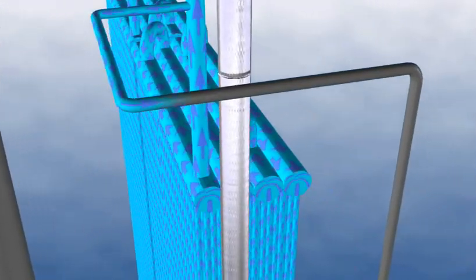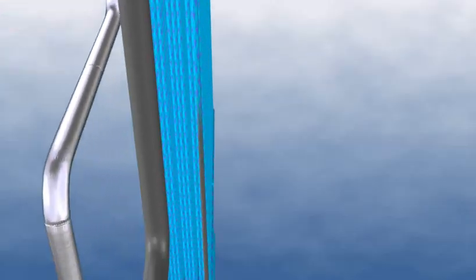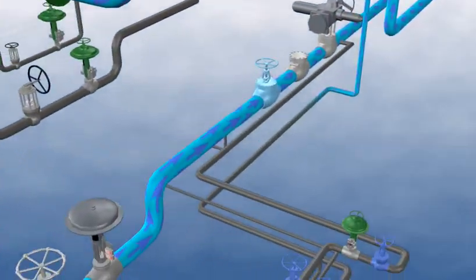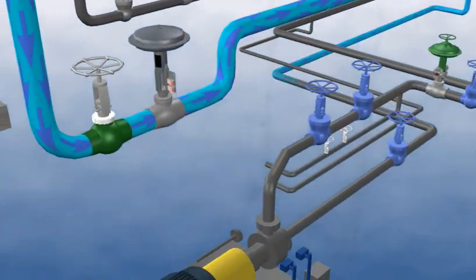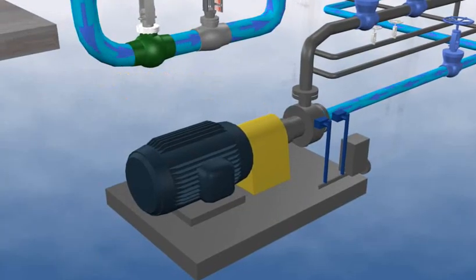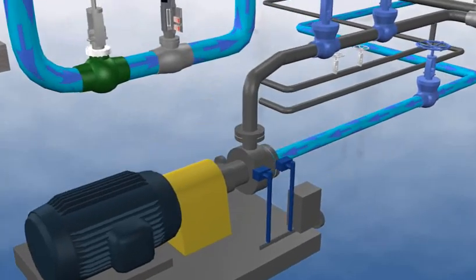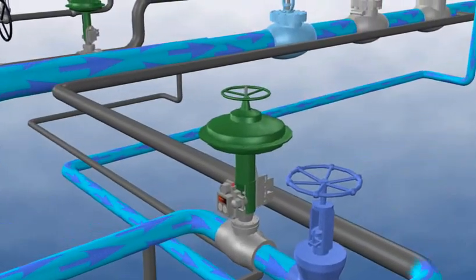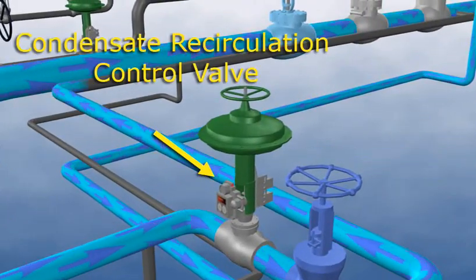A system has been provided by which a portion of the heated condensate from the discharge of the LP economizer can be recirculated to the economizer inlet. The recirculation is achieved by the economizer recirculation pump, and the amount of water recirculated is controlled by means of a control valve.